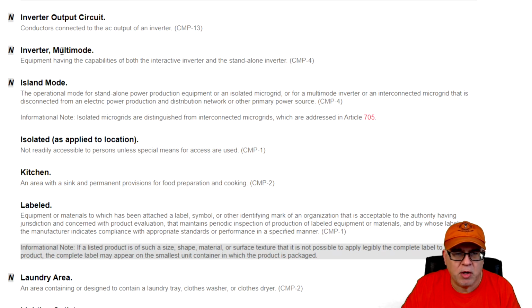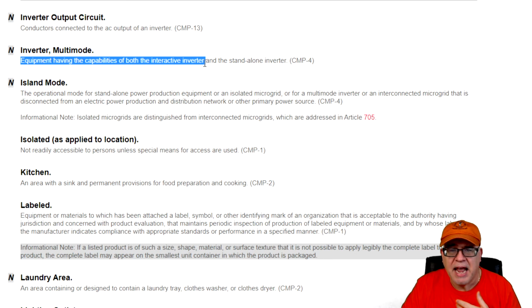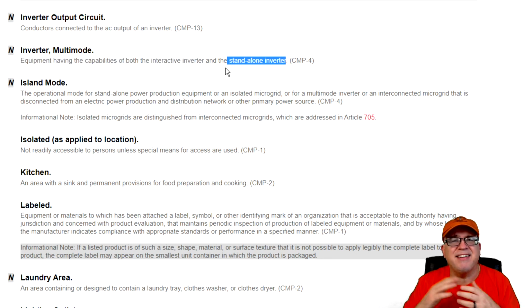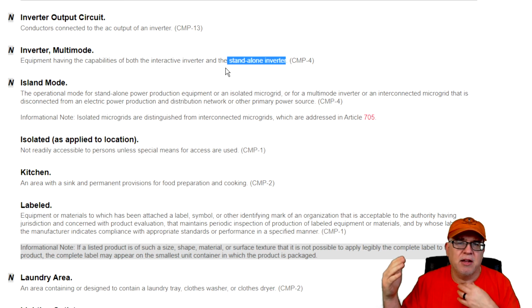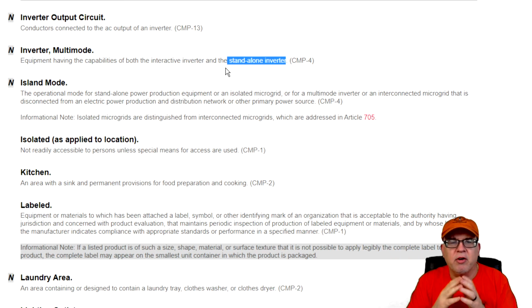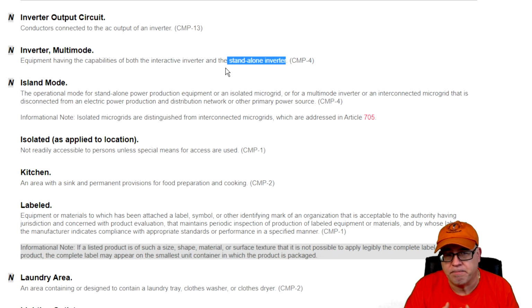Next, you have multi-mode, and that is basically equipment having capabilities to act as both an interactive inverter, that means interact with the utility, and it can stand alone on its own. It does not need to interact with the utility. In other words, you lose the utility grid and it switches over. So if it's multi-mode, it has the ability to work as a standalone, or it can work as an interactive inverter. Most of the ones that connect to the utility system are interactive inverters, but a lot of inverters, if they have a multi-mode feature, can operate and act as a standalone. It doesn't necessarily have to be connected to the utility to function, okay?